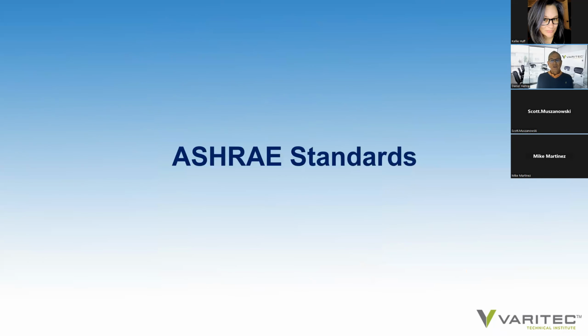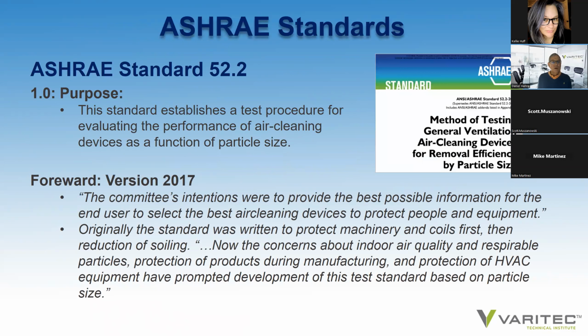So what are the ASHRAE standards that define the various conditions that a building needs to attain to maintain thermal comfort and better IAQ? Well, the ASHRAE standards involved start with Standard 52.2. ASHRAE 52.2 defines the testing methodology of filters. They assign the MERV rating for filters. It's conventional in HVAC to use a MERV 8 filter.